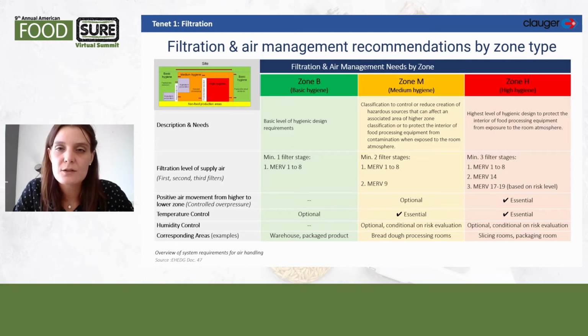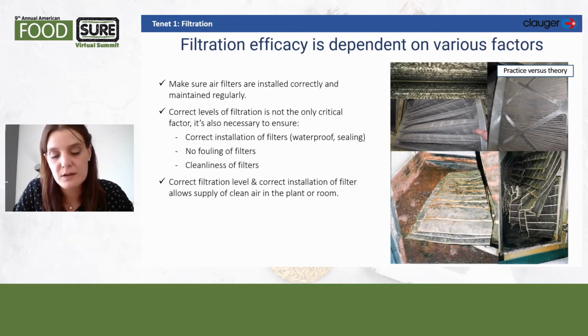Here you need to have 3 filter stages, especially the filter MERV 17 to 19, depending on what your product is. You have to control the temperature and the humidity, and also it's recommended to control the positive air movement from higher to lower zone in order to avoid mixing of air between each zone. So you can have the right level of filtration in each zone, but it's really important to ensure that the filters are installed correctly, because if they are not, you can have air bypass and contaminant from the exterior in your room. It's also important to maintain these filters regularly, because you can manage your energy consumption because of the pressure.